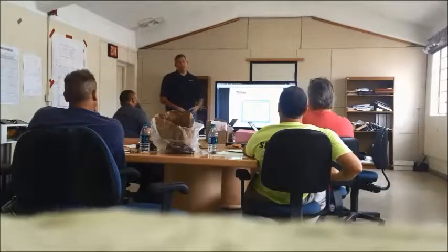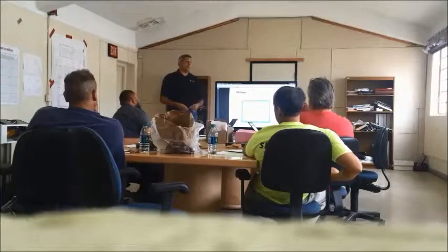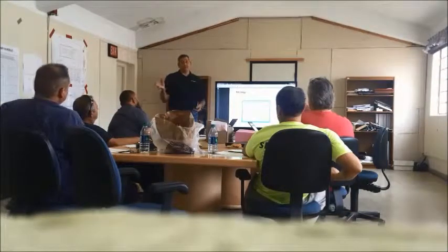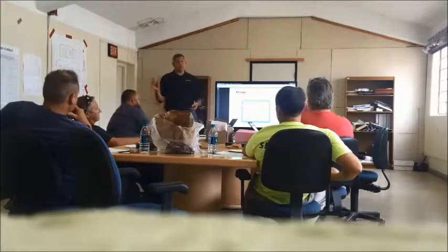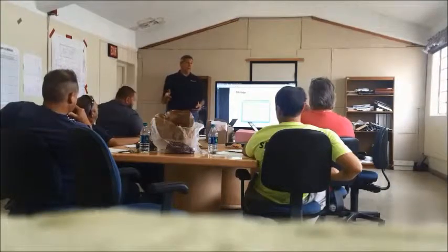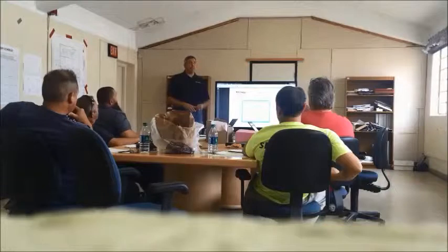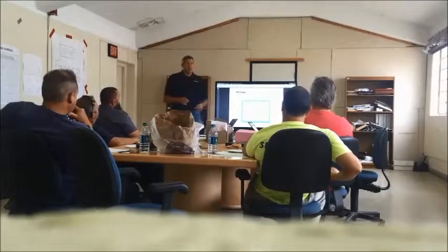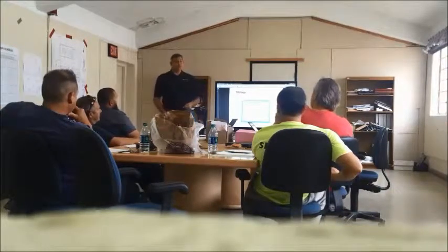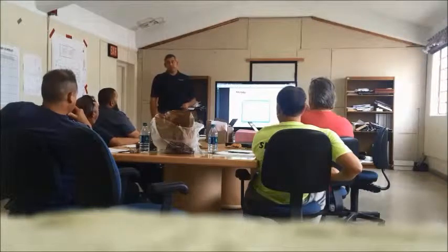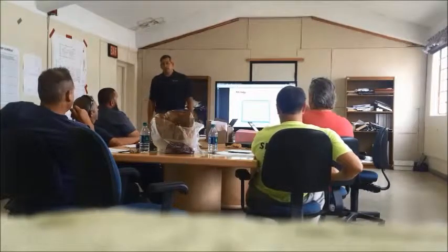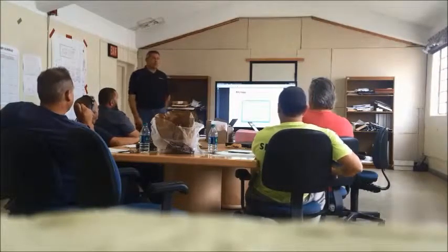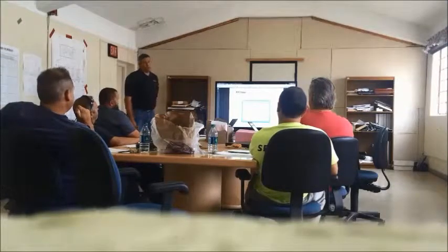If something truly goes wrong and you need to run the fans in bypass, it's a change in the program, just 99, I think it's 9906. You can say bypass active as far as in the bypass section. Then you can personally enable it yourself. I don't like to see it in an automatic transfer. I just care to disable it. I don't want anybody pushing one of the buttons that says auto transfer and all of a sudden it transfers, then we got other issues that cause us more maintenance work. So that's what I normally do.